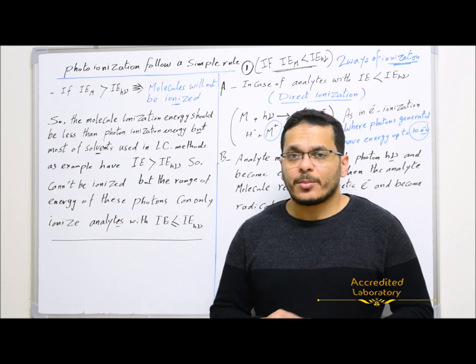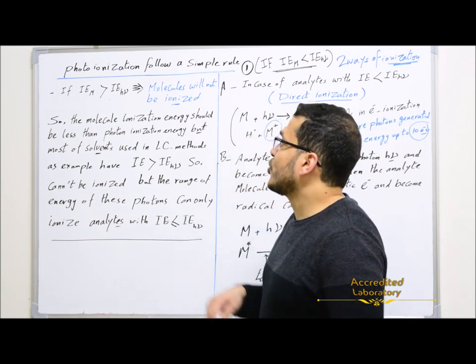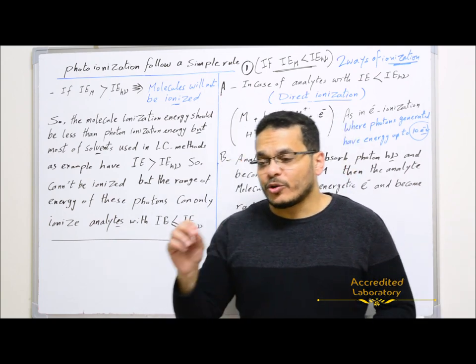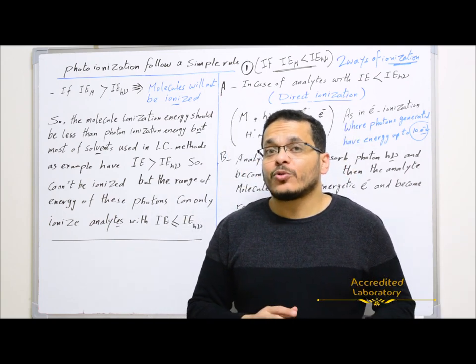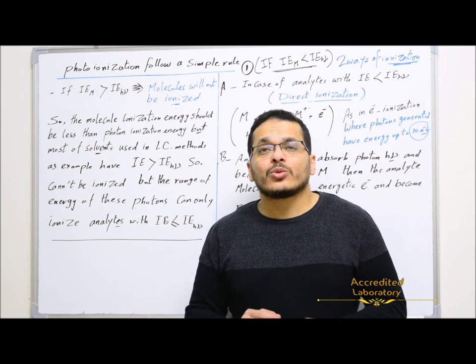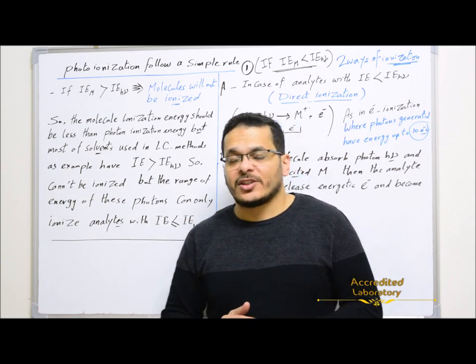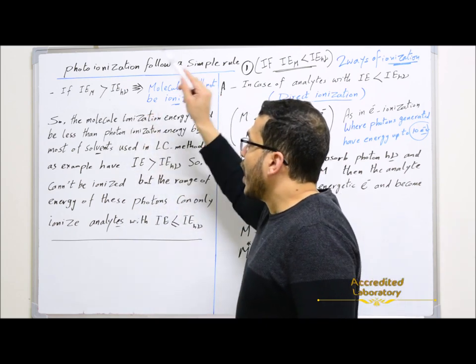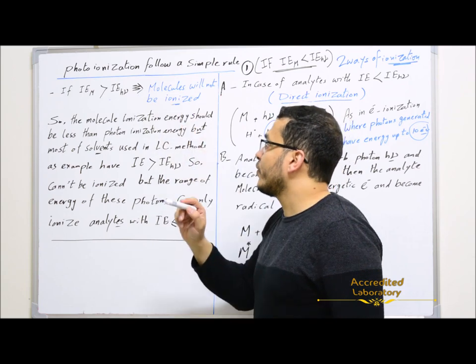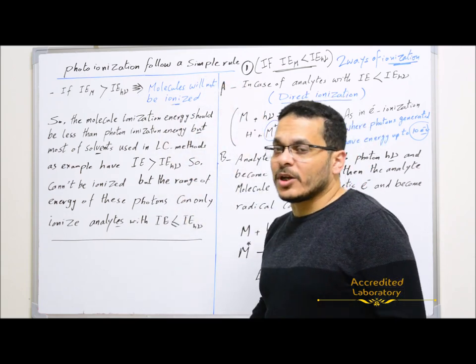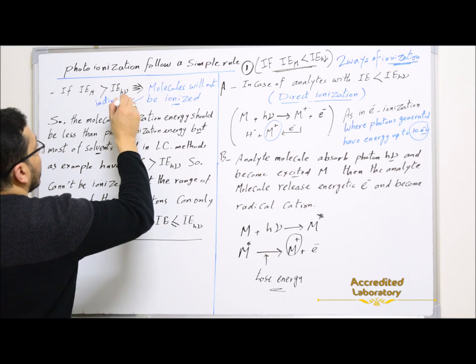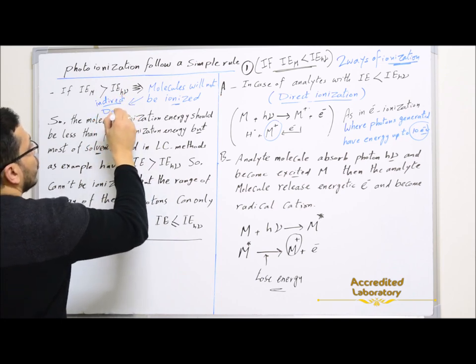But how does this ionization happen? Photo ionization follows a simple rule. If the ionization energy of the molecules is lower than the ionization energy of the photons, the analyte molecules can be ionized by direct ionization. But if the ionization energy of the molecules is higher than the ionization energy of the photons, molecules will not be ionized by these photons, but there will be indirect ionization by using something called a dopant.